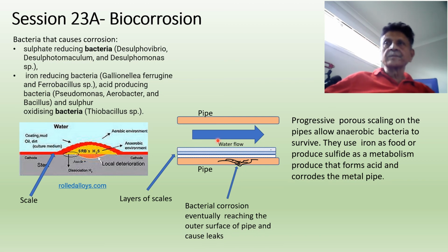So as soon as the chlorine or antiseptic or disinfectant is removed, these bacteria will come out and consolidate the rest of the areas. So bacterial corrosion is very serious. It is very important that when you look after the cooling towers, you try to have as low bacteria as possible, because eventually you still will get corrosion by the bacteria.